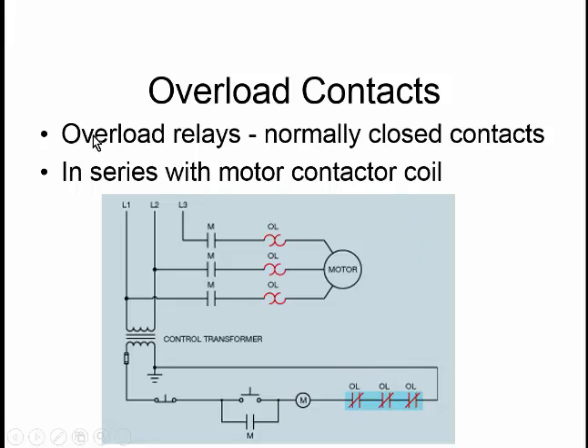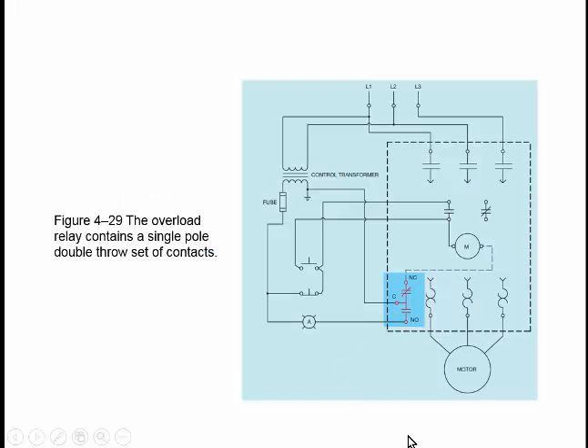Overload relays are normally closed in our circuits. See how they have the slash through them? Once these heat up, they become open. They're in series with the motor contactor coil, and the sensing elements are also in series with the actual motor. Here's another picture of them. Sometimes you don't just have normally closed, but you have some normally open contacts, and you can use those for other things. In this case, we're turning on a light to alert the operator that there's been an overload trip.